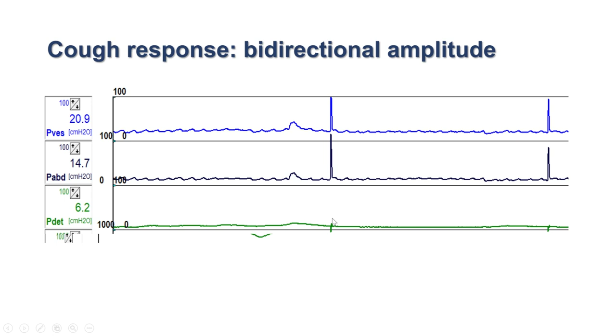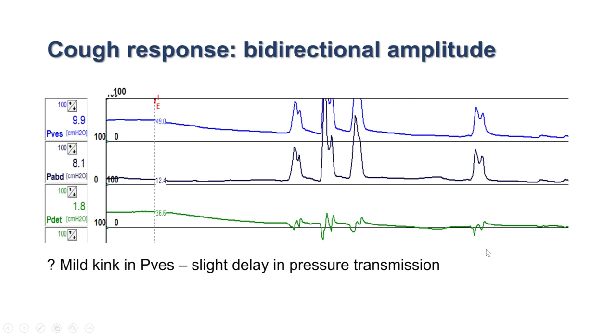Now the cough response is checked, and ideally there should be either no response in P det while coughing, or a small, sharp bidirectional movement of up to 5 centimeters of water. Bidirectional movement beyond this in the P det during coughing, or unidirectional movements, are not acceptable, and we should look for any kinking or any air bubble in one of the channels. A unidirectional cough response is generally seen when one of the measurements, whether P abdomen or P ves, is not showing it properly.